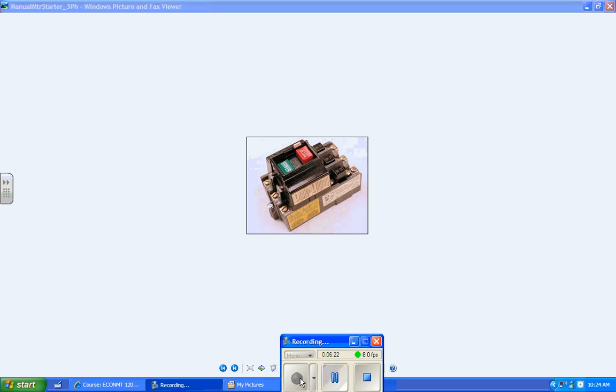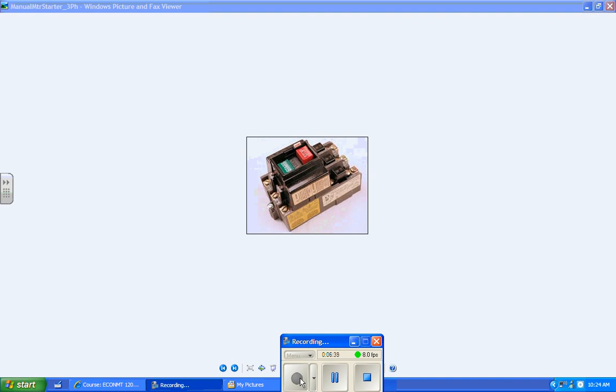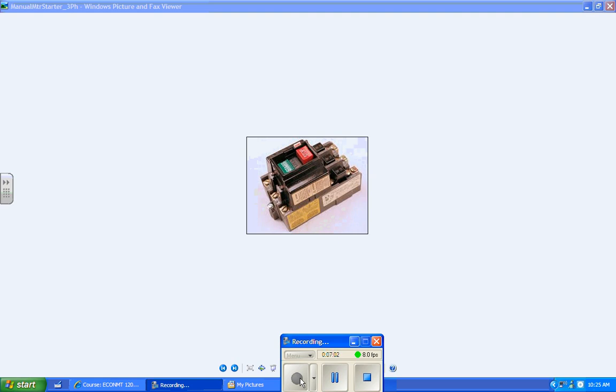I want to talk about a manual motor starter that has a low voltage release. That means when the power drops out, it opens the circuit. Generally speaking, a manual motor starter, once you start it, if the power goes out the motor will stop, but when the power comes back on it'll resume running. That's called not having low voltage release. So a manual motor starter generally doesn't have low voltage release.